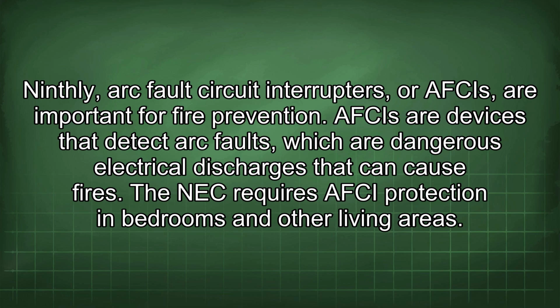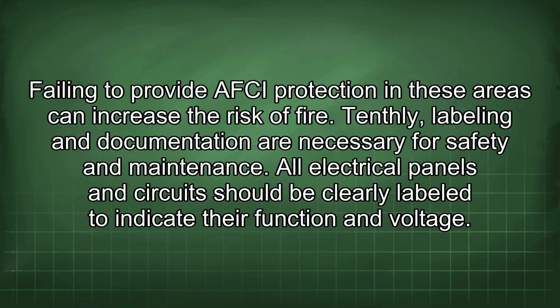Ninthly, arc fault circuit interrupters, or AFCIs, are important for fire prevention. AFCIs are devices that detect arc faults, which are dangerous electrical discharges that can cause fires. The NEC requires AFCI protection in bedrooms and other living areas. Failing to provide AFCI protection in these areas can increase the risk of fire.